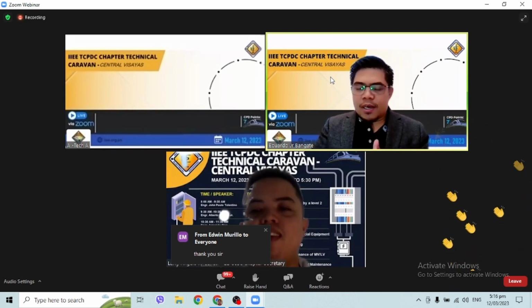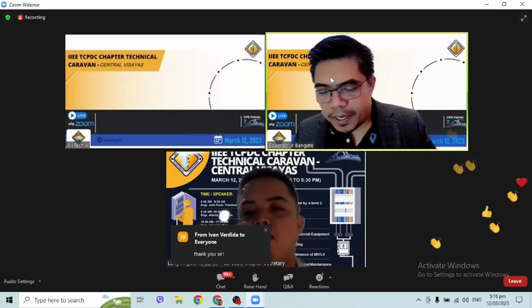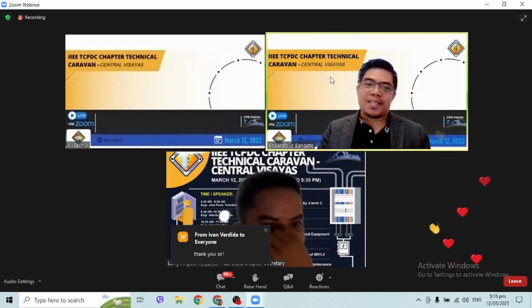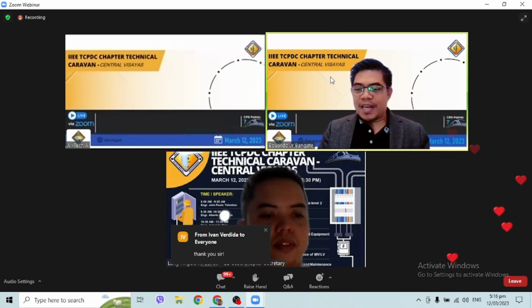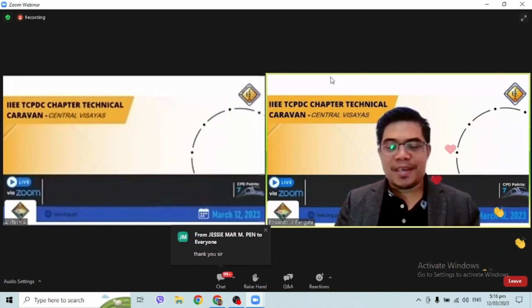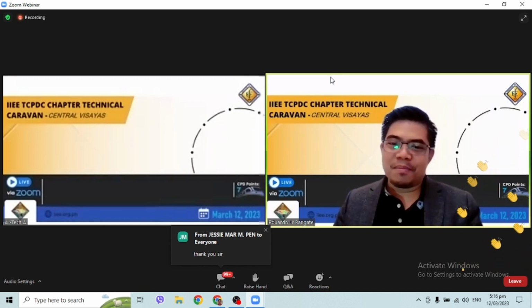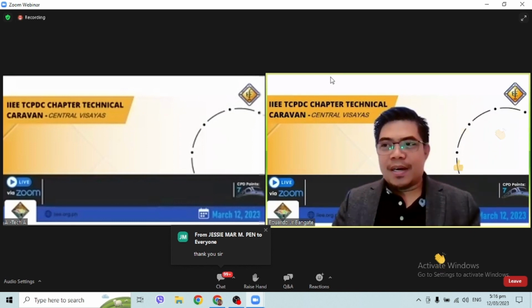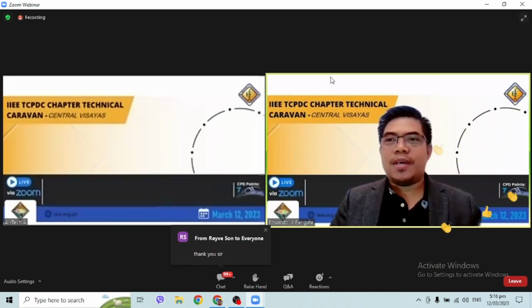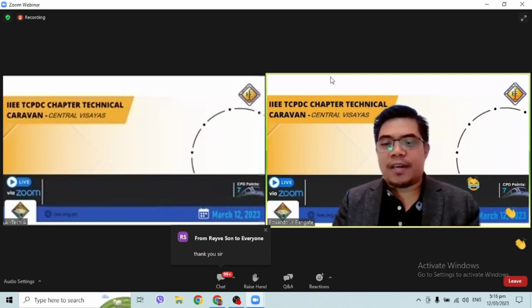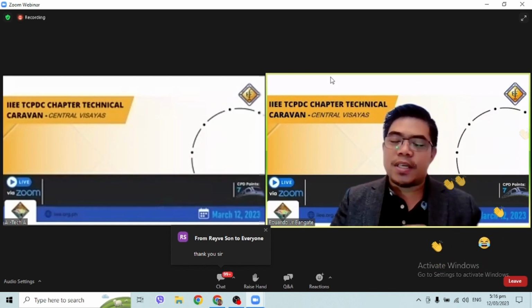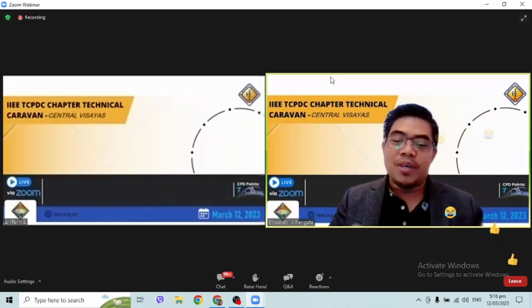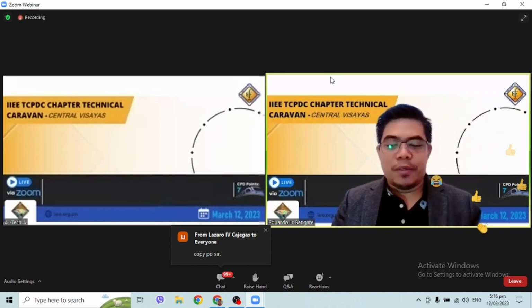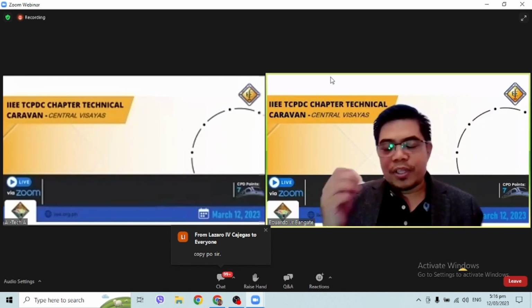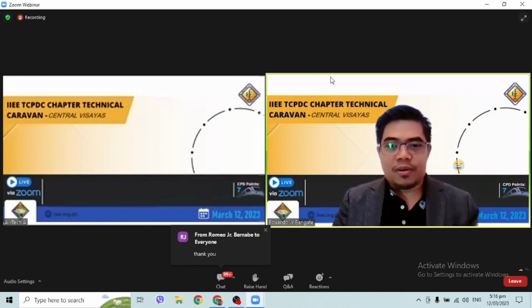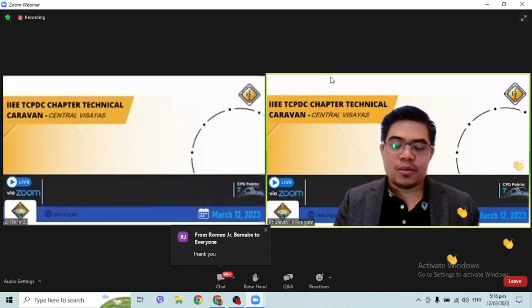Okay. Based on my experience, if the weather is very cold, there is something we do to reheat the winding, okay? But that is normally done only in very extreme cold weather. I'm not sure where it was taken from, because if you rotate the generator, it will produce a residual current. I don't think there's a need to inject current into the generator, even if it has not been used for quite a while. It will give you the needed current for the triggering voltage for the alternator, in case you have a shunt type excitation system for the generator. So I'm not very sure, really.